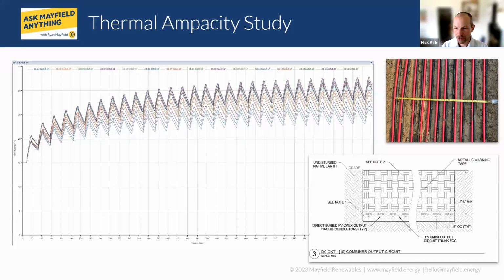The first study we performed was the thermal ampacity study. This allowed us to take the developer's trench detail. In this case, we originally had 8 inches on center between the direct buried circuits. By using ETAP, we were able to model these circuits by taking into account this layout, the soil temperature at the desired conductor depths, and soil thermal resistivity that we got from a geotech report. And we also included SAM modeling. The SAM modeling allowed us to produce a transient load profile so that we can account for the daily cycling of the PV asset.